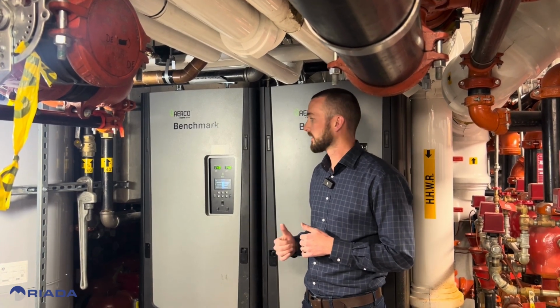Another thing we can do with the edge is we'll take an O2 input, an O2 sensor. We're measuring the oxygen level of combustion right in the combustion chamber. What that allows us to do is dial in the optimal O2 percentage of combustion using the air-fuel mixture. So if we have too little O2, that's dangerous. We could have too much fuel, unburnt fuel, going into the stack. That's dangerous. So one, we're being as safe as we can here. If we have too much O2 as a result of combustion, that's not good for efficiency. A higher O2 percentage lowers the dew point of the flue gases, meaning we need a lower return water temperature to the boilers just to condense. So if we have that optimal O2 percentage as a result of combustion, it's the most efficient way to heat your building.